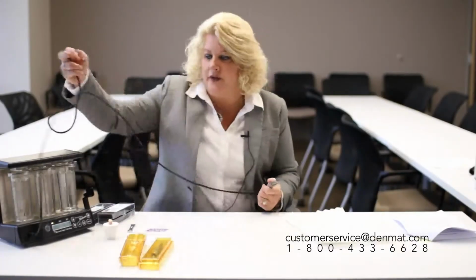So you're having trouble with your Pro-Select Platinum or your Pro-Select 3 with your handpiece. What's happening is the water is just shooting straight out of it, it's not creating a fine mist, and the tip is not vibrating. Let's look at a couple of things that you can do in the office to see if you can get some resolution before you have to call us here at customer service.